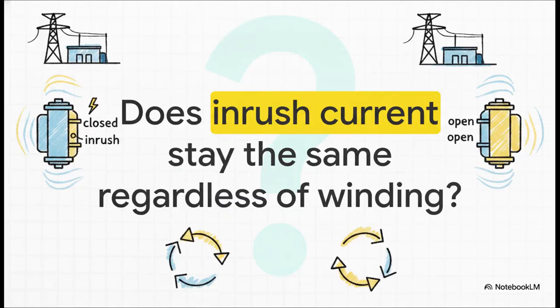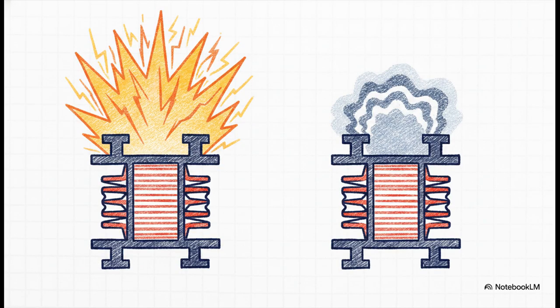So let's lock this concept in with one last check. If you have a single transformer sitting out there in a substation, does the inrush current multiplier stay the same regardless of which side you close the breaker onto first? Nope. It behaves entirely differently. Because the inner winding sits in a zone of lower air core reactance, energizing from the inside out causes this violent inrush current that can spike 10 to 20 times the rated current. But if you energize that exact same transformer from the outer winding, the higher air core reactance actually chokes the spike, limiting it to maybe 5 to 10 times the rated current. Same transformer, same nameplate, but a totally different behavior on the grid, based purely on geometric placement.